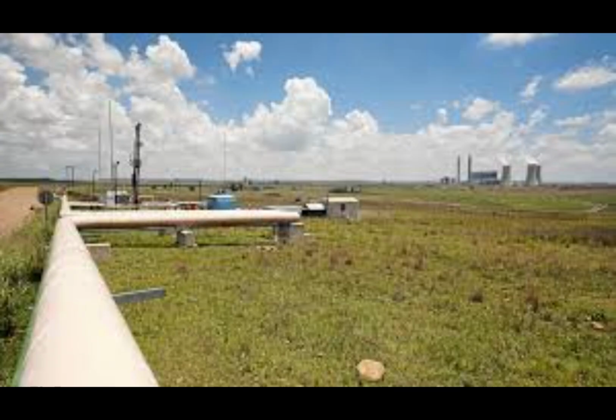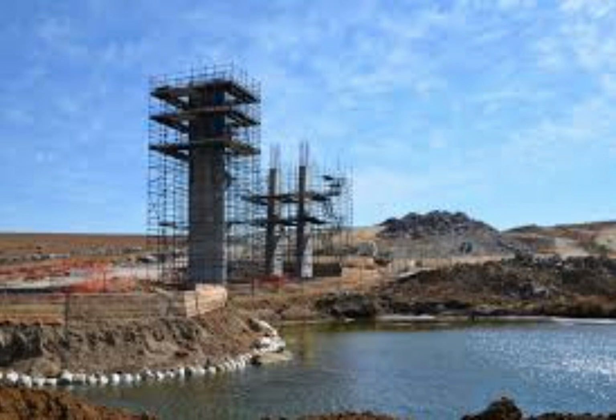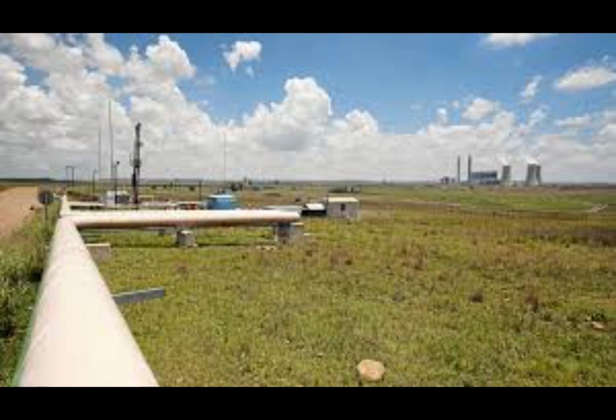Underground coal gasification. In addition to coal, the Majuba Power Station is fired by syngas produced by underground coal gasification at the nearby Majuba Demonstration Facility on the Majuba coal field. The 3,000 to 5,000 cubic meters per hour, 110,000 to 180,000 cu ft/h, pilot plant was commissioned in January 2007, and the first electricity was generated from the underground coal gasification gas on May 31, 2007. Produced syngas is transported from the facility to the power station by a 7-kilometer, 4.3 miles, pipeline with a diameter of 600 millimeters, 24 in. There is a plan to build a 1,200 megawatts commercial generation facility.